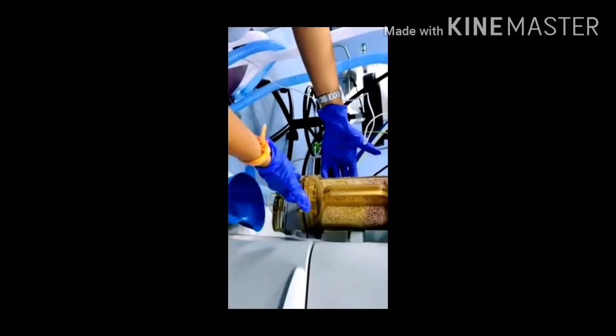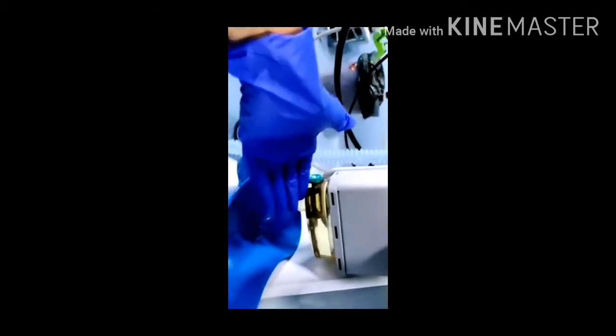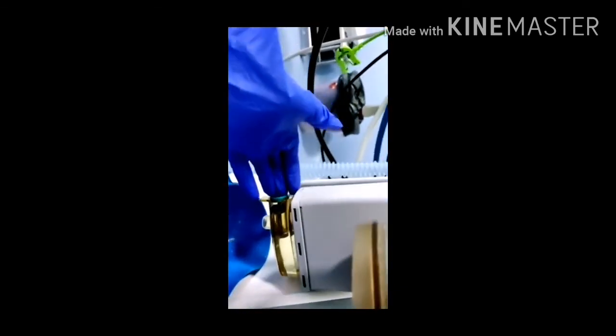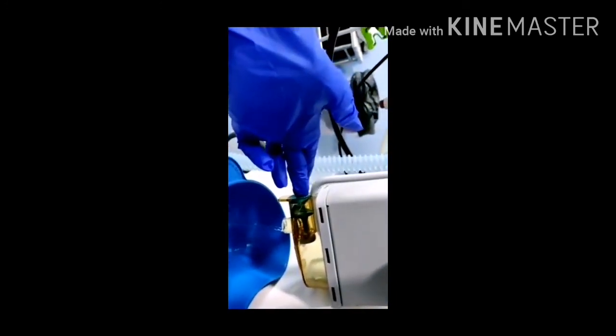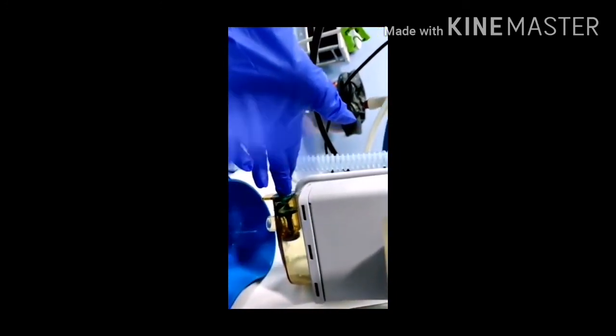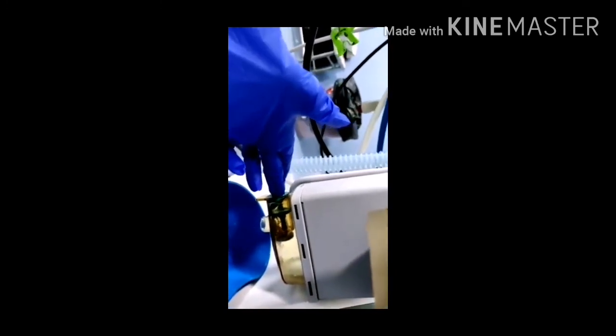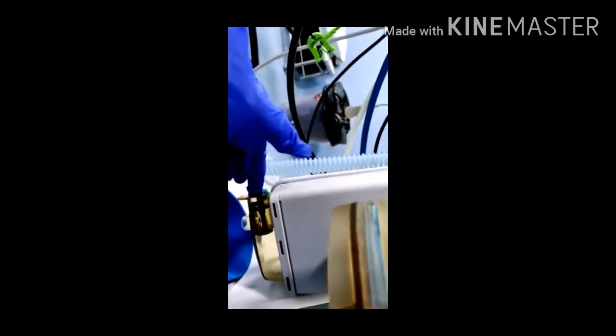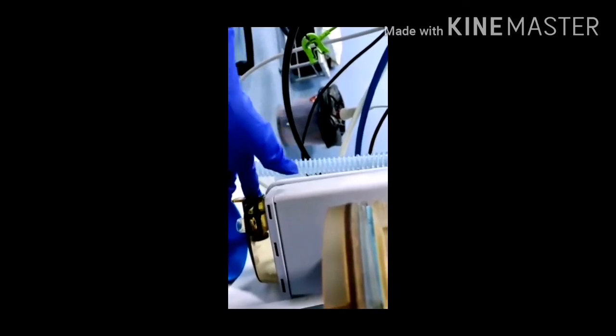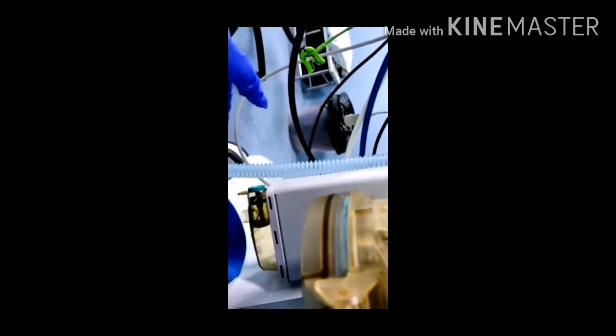Besides the canister, there is a dispenser assembly which accumulates the water or vapor that has been collected by the CO2. It is passed on to the assembly, and the water is collected below. It should be taken care that from time to time this water is released by pressing this green button over here, or there are chances that the water remains in the assembly, or there is chance of backflow which would damage the system and the machine. So make it a point to release the water whenever a case is done. Here the water is released.